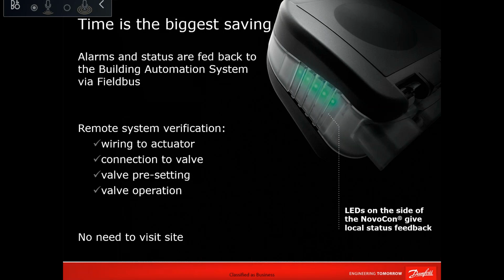Now, mixing Novocon and standard actuators, it's not a matter of can we. It has to be, because if I take a normal building, I have areas like residential which are standalone. You will have a normal standard actuator, locally controlled, 3-fan speed motor, etc. It is not connected to the BMS, but the common area is connected with the BMS. You will be using the Novocon there. So here you have a mix between Novocon and standalone or standard actuator. So yes, you can mix with no effect on performance on either actuator. Both will be fine.